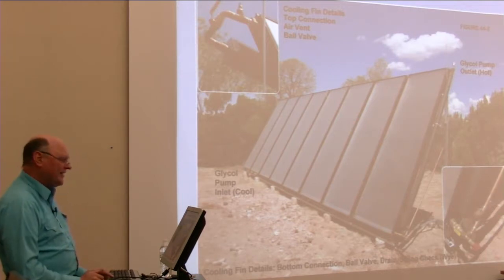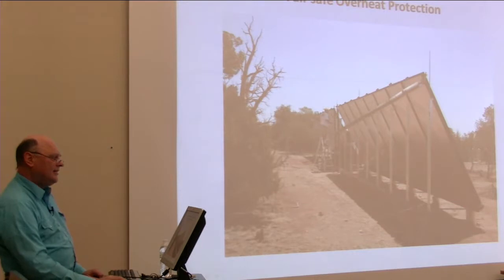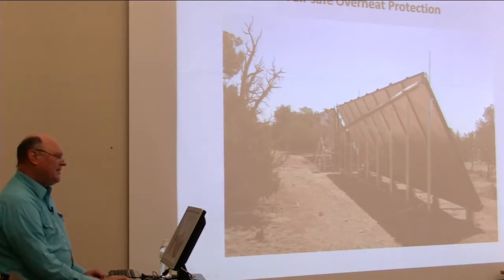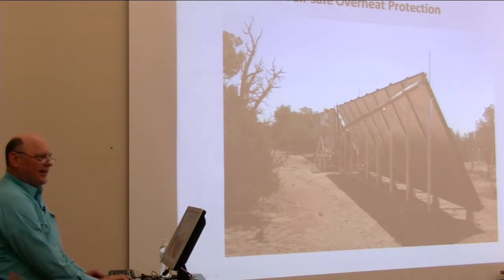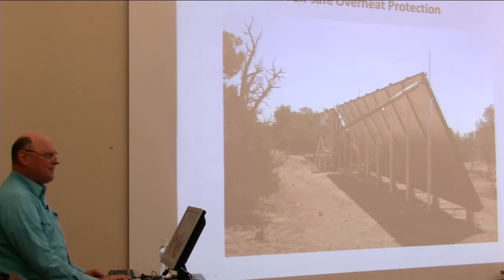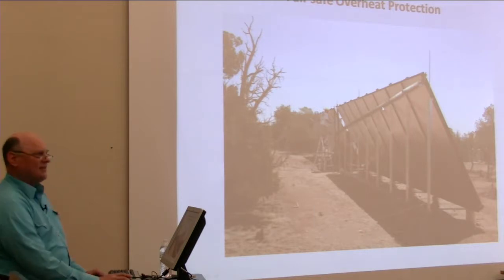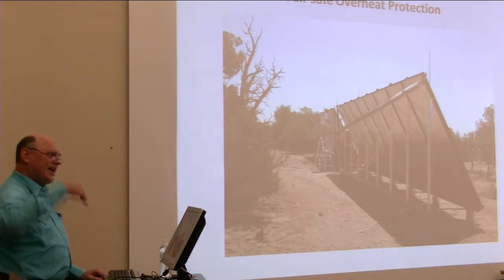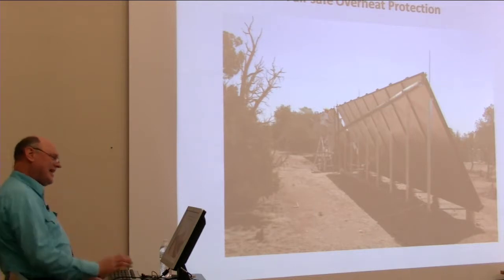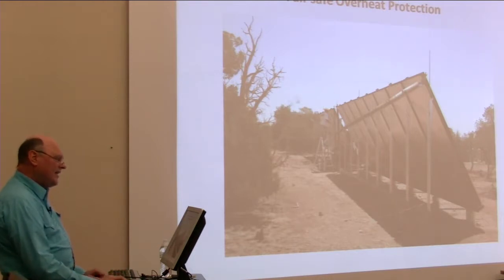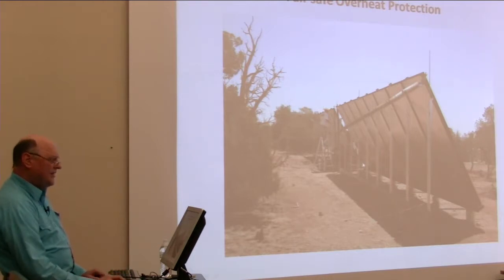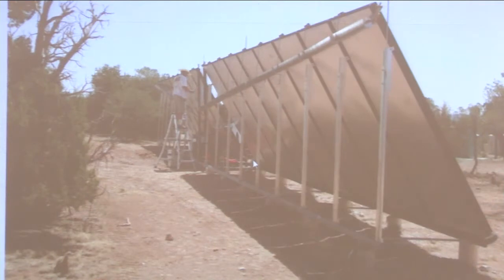Here's the back of the collectors, just to make this more clear. It comes out of the top when it's not being pumped, rises by natural convection, slides into these fins. The fins give the heat off to the air. The cooler liquid becomes more dense and drops by gravity down the pipe because the pipe is tilted. So it slides downhill because it's dense and heavier fluid. And then it reaches this other end where it goes back into the bottoms of the collectors.